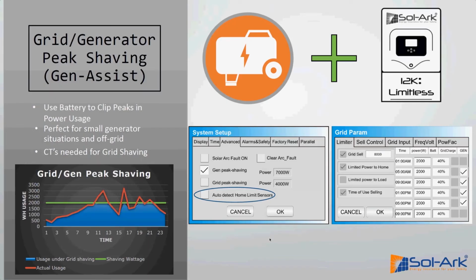All right, and then some other things we can do with generators and the grid is we can do peak shaving or Gen Assist. And so peak shaving is pretty straightforward. You're going to use that for customers that have demand charges. You can set a threshold value, and the Sol-Ark will step in with the battery power to keep the property's power usage below whatever your threshold is. So kind of like this chart on the left here, the red line is what you would have been using, and the green line is the threshold, and then the blue is what you actually wound up using with the setting enabled.